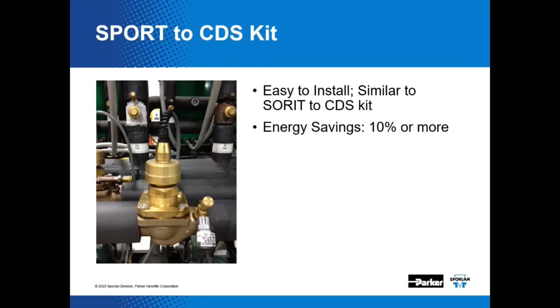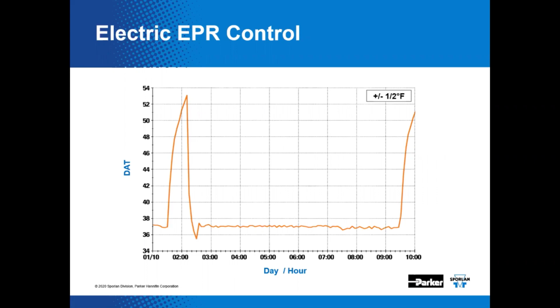Supermarkets can realize some pretty decent energy savings. I've been told up to as much as 10% or more. Now, how well does it work? Well, here's a log of data that was acquired on a system with an electric evaporator pressure regulator. It was a medium temp system. This graph displays case temperature in degrees Fahrenheit and discharge air temperature versus time. The set point was approximately 37 degrees.